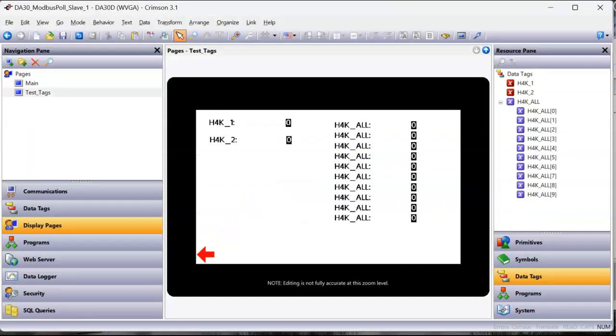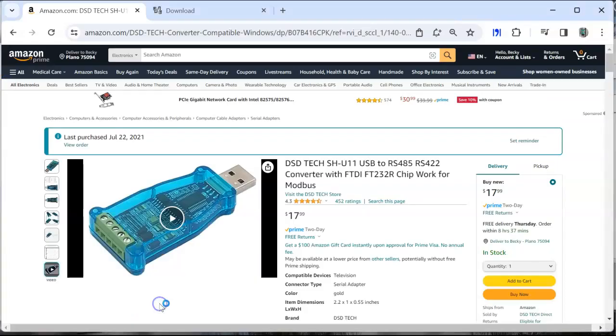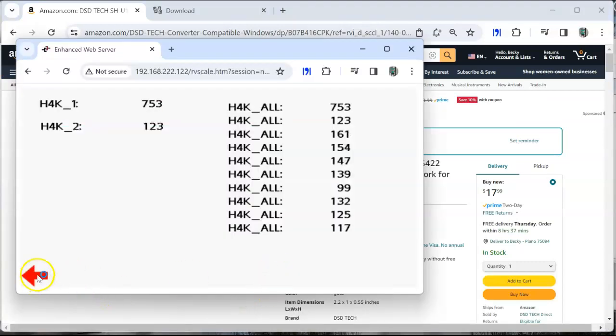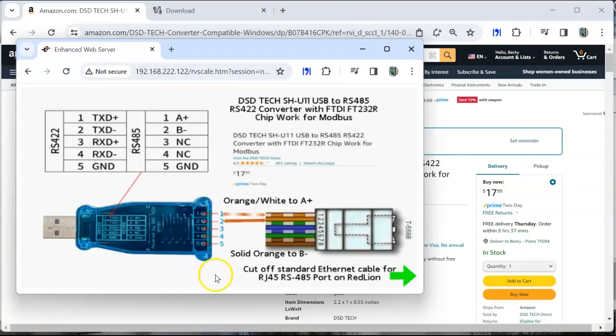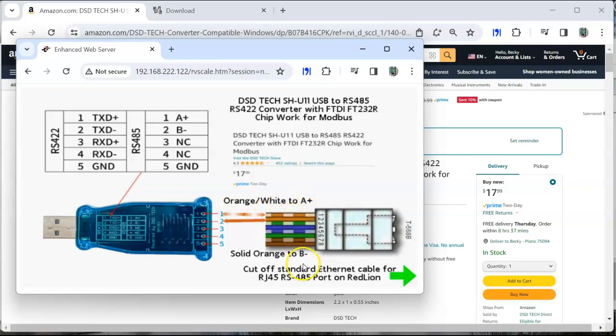Oh, the one thing I will tell you, I usually, I literally just take an ethernet cable whenever I'm doing RS-485 comms and I literally cut off one end of the ethernet cable. And I use pins one and two, which is usually the orange white is pin one and the solid orange is pin two. And the orange white is your A plus and the solid orange is your B minus. And I literally wire the Red Lion unit. When this happens, you'll get red and green LEDs blinking real fast on the RS-485 port on the Red Lion here.